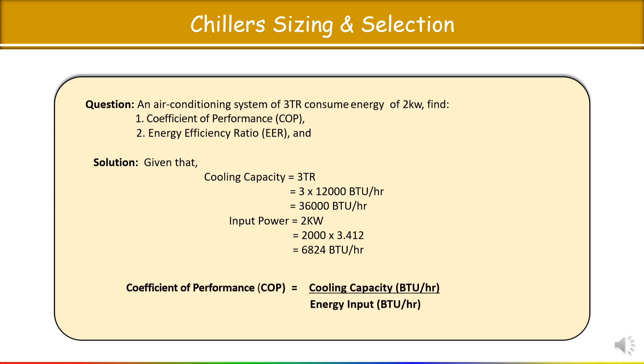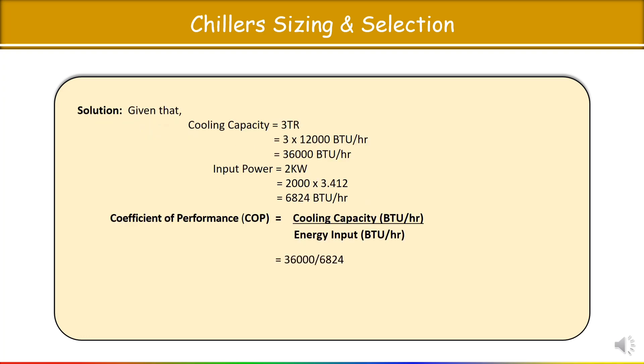To calculate COP, the formula is: COP = Cooling Capacity (BTU/hr) ÷ Energy Input (BTU/hr). Substituting the values, you get a COP of 5.27. The greater the value of COP, the better for the machine. So from a manufacturer catalogue, if you get 5.27, it's better to select a chiller with 5.5 if available, since higher COP means better efficiency.